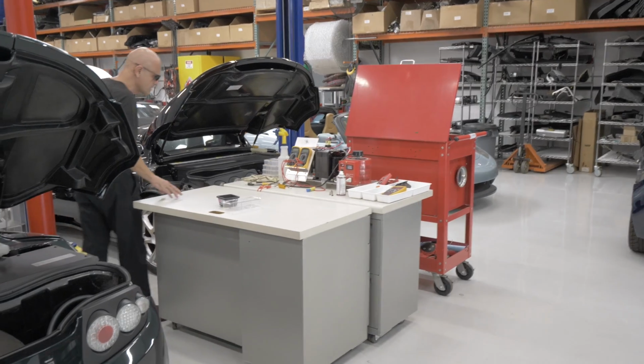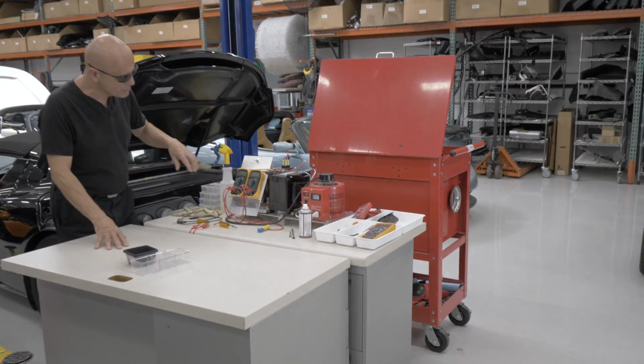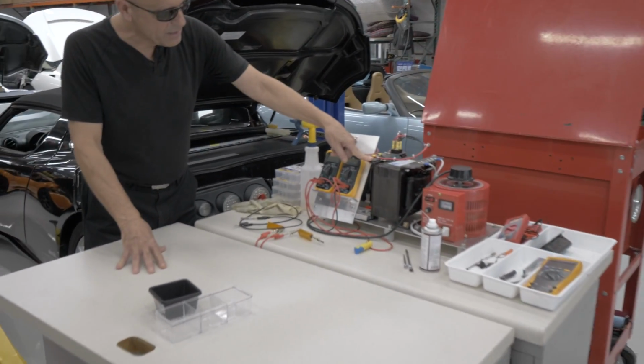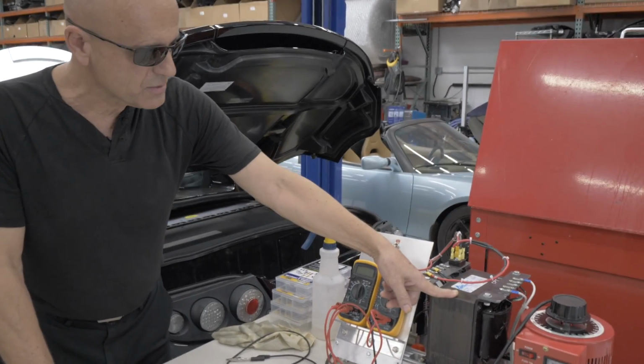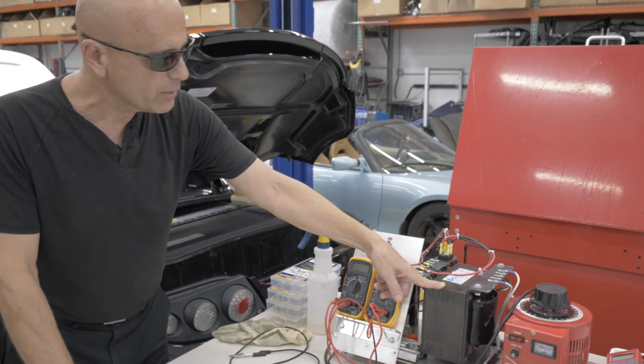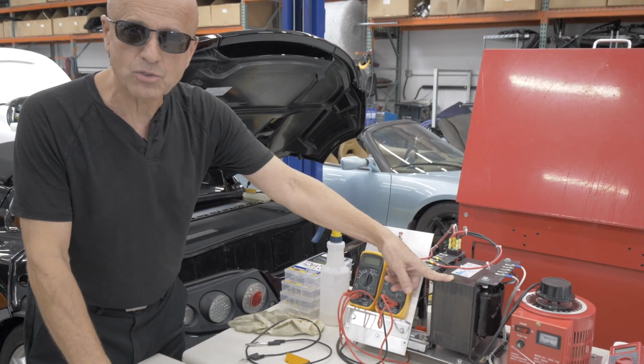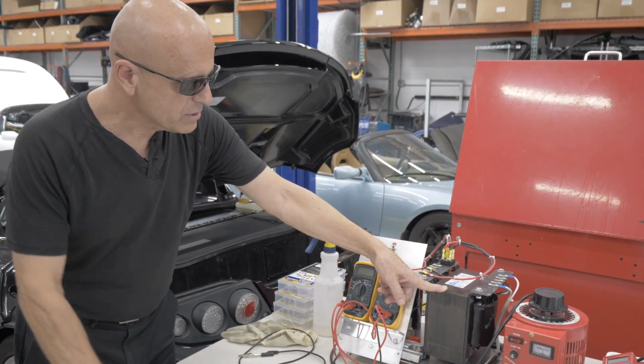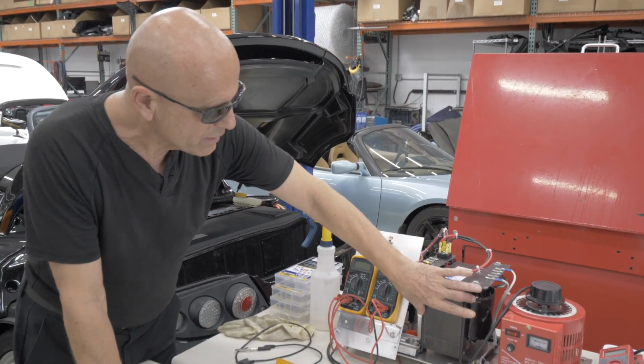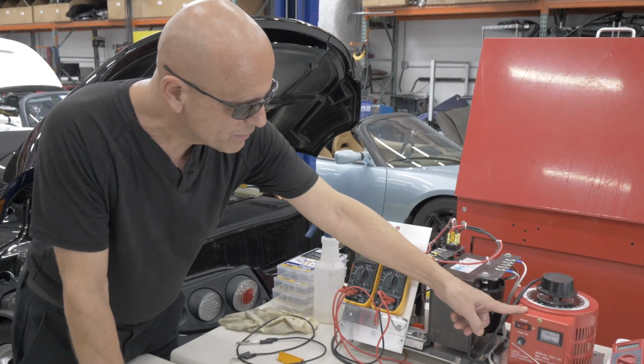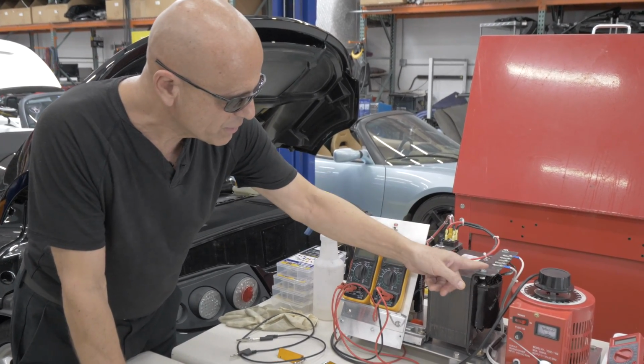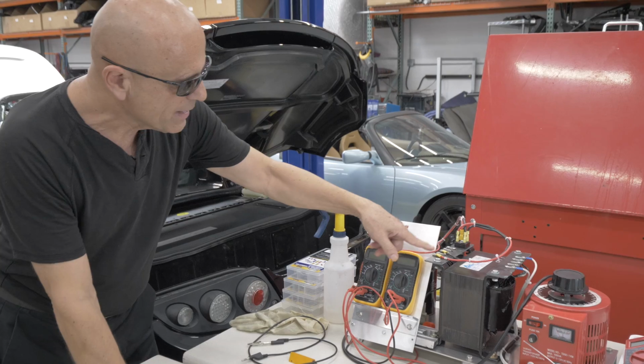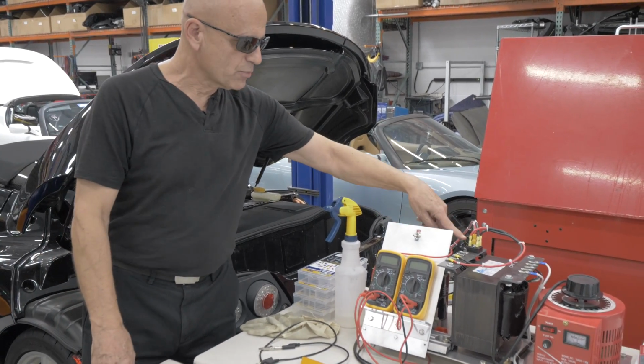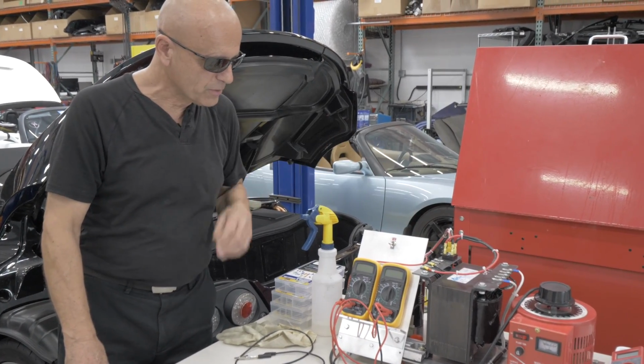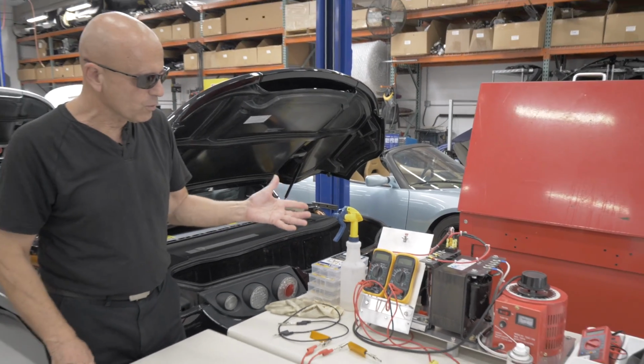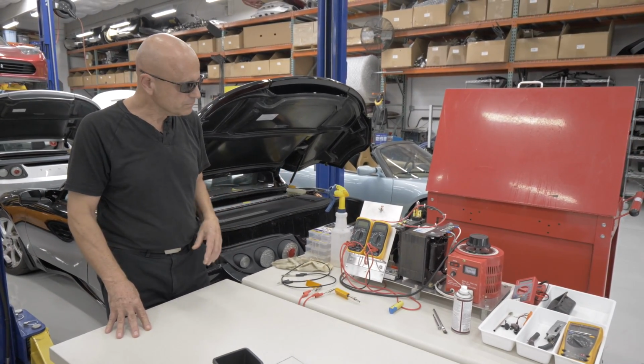Here's an example of how we did this. Inside 480 volt UPSs, there's a 480 to 120 volt transformer to power all the instrumentation in the UPS. We simply inverted the transformer, feeding it with a variac, 0 to 130 volts on the 120 volt side. The 480 volt side then goes through a rectifier and capacitor filter, and we're able to create a variable 400 volt power supply.